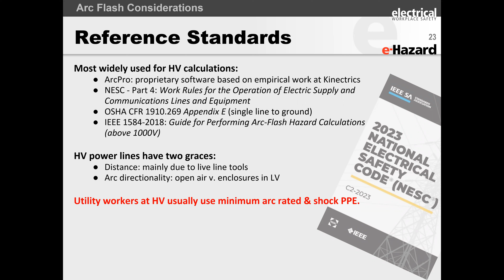Okay, folks, this is just continuing on the LV tables. NESC does have rules - okay, another contentious slide here. What they say is that 8 calories per square centimeter should be adequate for all voltages below 250 volts, and they note variability between 251 to 600 volts. You can read these four bullet points - sometimes you get 40 calories, sometimes you could get more than 40, sometimes you get less than 40.